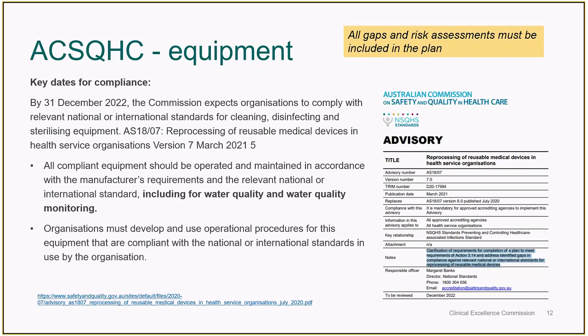Now, the next key dates in that advisory are related to water quality. By the 31st of December 2022, they expect for accreditation that hospitals will comply with the requirements for monitoring water quality. So as you replace equipment used in the cleaning, disinfecting, or sterilization processes, water quality requirements should be included in the planning and risk assessment undertaken. All of those gaps and risk assessments have to be included in the plan. Now, just a little hint around water quality: everybody pushes RO water, but RO water sometimes will still not resolve your water quality issues.